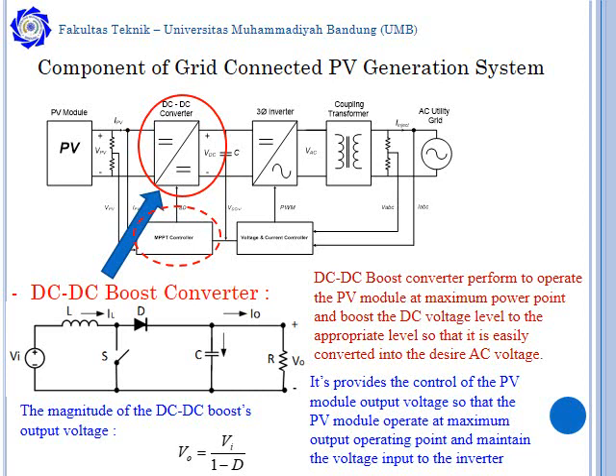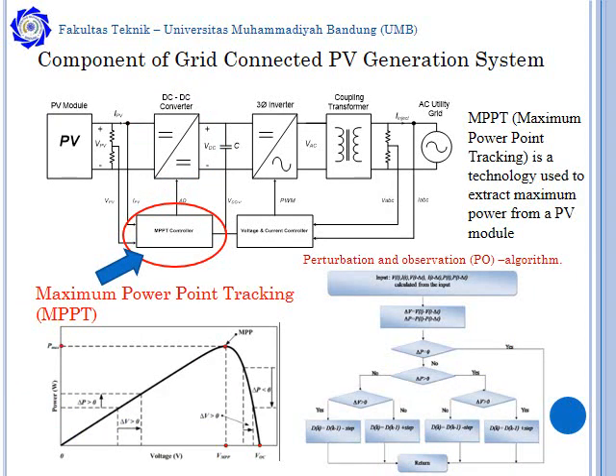The DC-DC boost converter provides control for the PV module output so that it operates at the maximum output operating point and maintains the voltage input. The maximum power point tracking is a technology used to extract maximum power from the PV modules. The method algorithm used in this system is the perturbation and observation method.